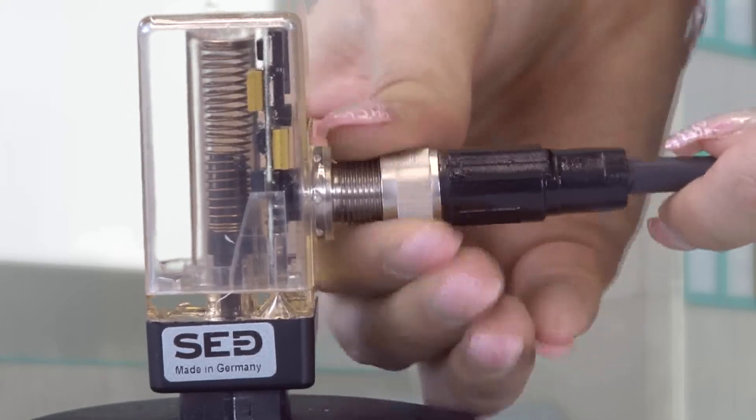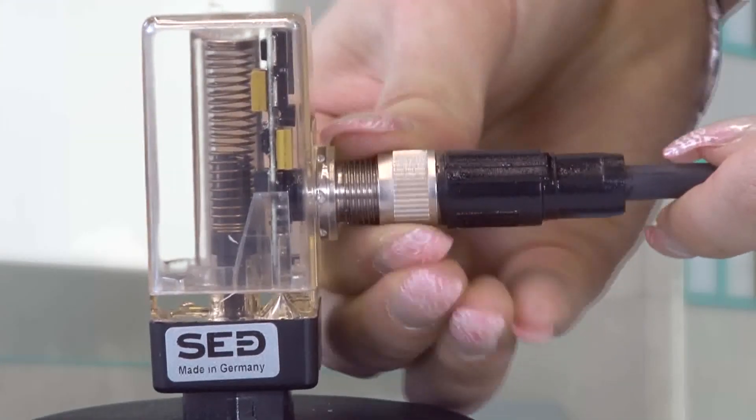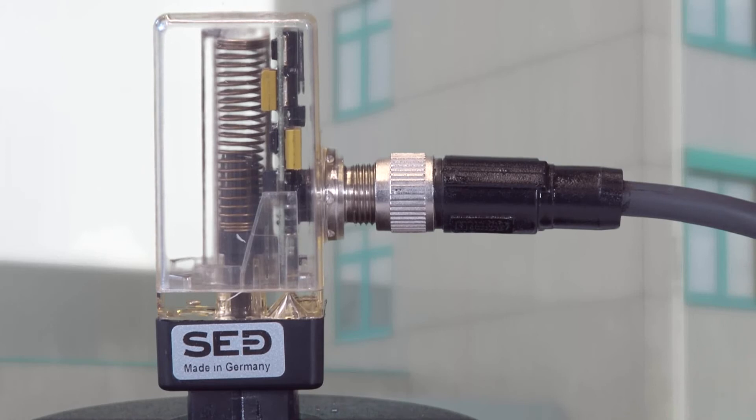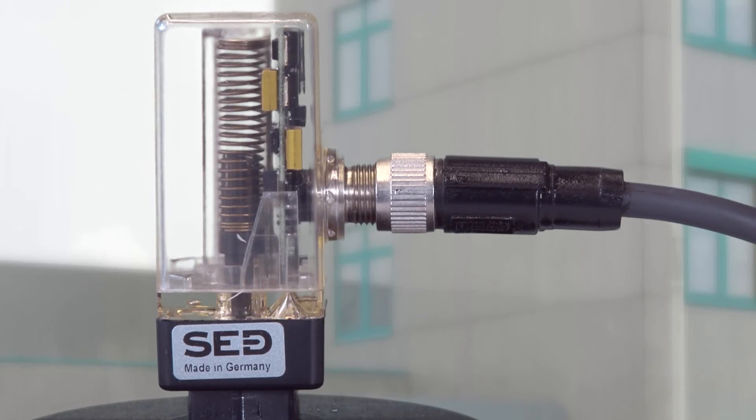Thread on the 5-pole plug and supply the electrical voltage to the limit switch. The electrical limit switch is put into programming mode by supplying voltage on pin 5. The programming mode is indicated by permanently shining violet.